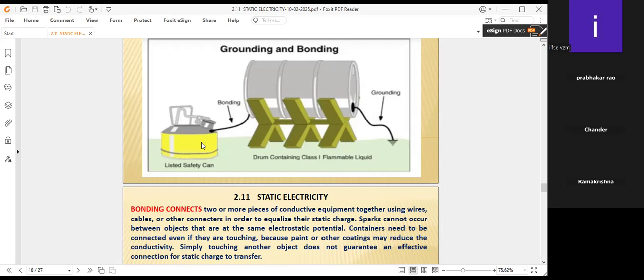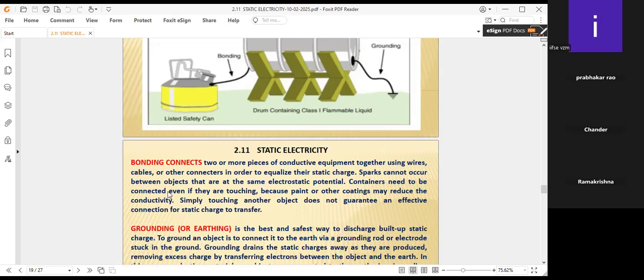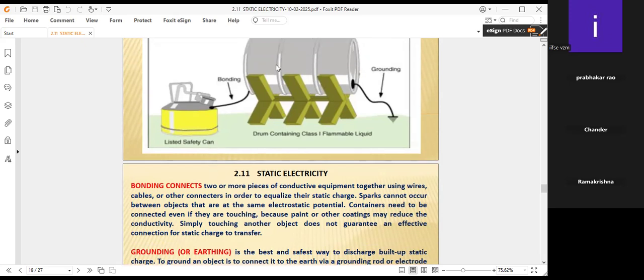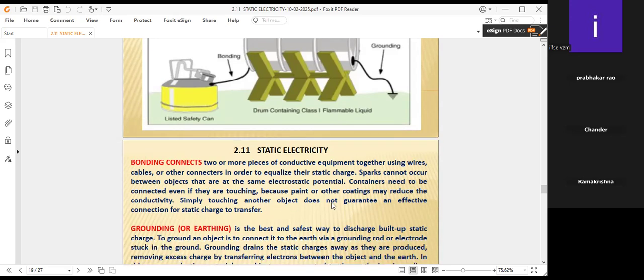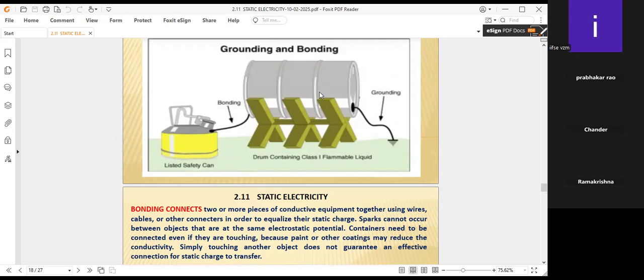What the gentleman is telling is 100% right: where flammable liquids are there, both bonding and grounding are very, very important to connect. That's why the containers need to be connected even if they are touching, because paint or other coatings may reduce the conductivity. Here the painting is there on the drum and the nearby equipment. The painting cannot give much guarantee to attract the static charges. Simply touching another object does not guarantee an effective connection of static charges, because I cannot guarantee that the paint, the insulation, or the earthing will take care of it.